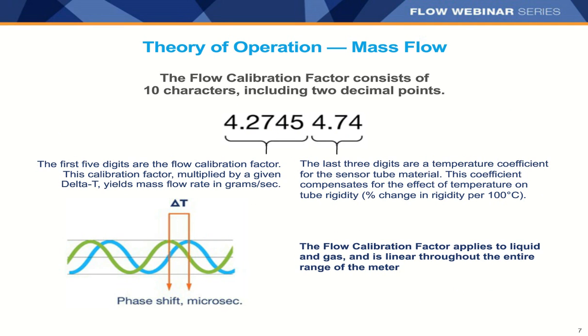The flow calibration factor is one of the most important pieces of a Coriolis meter — it's the thumbprint that characterizes the whole meter. It's ten characters including two decimal points: the first five digits are the flow calibration factor, which multiplied by a given Delta T yields the mass flow rate in grams per second. The last three digits are the temperature coefficient for the sensor tube material, compensating for the effect of temperature on tube rigidity — percent change in rigidity per 100 degrees Celsius change. This is very linear: a 10% change in the factor results in a 10% change in flow.